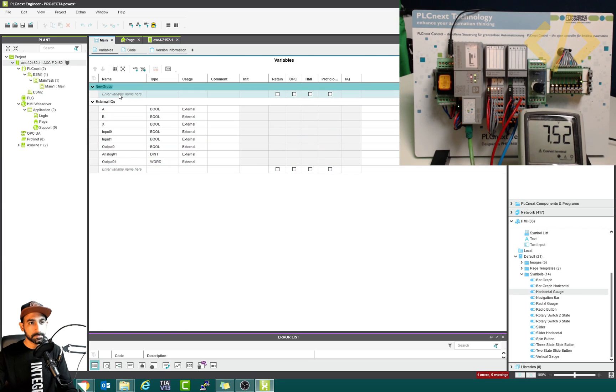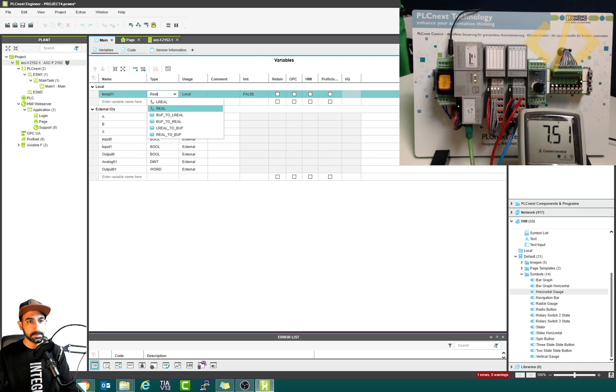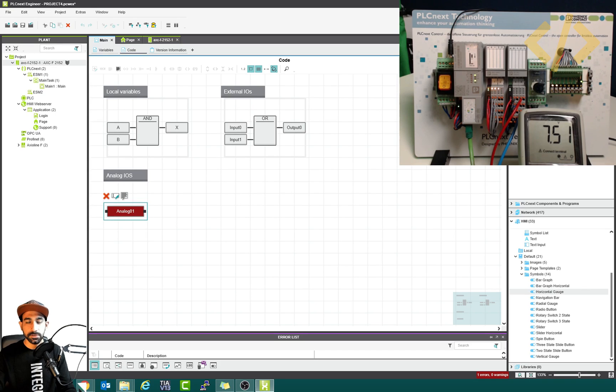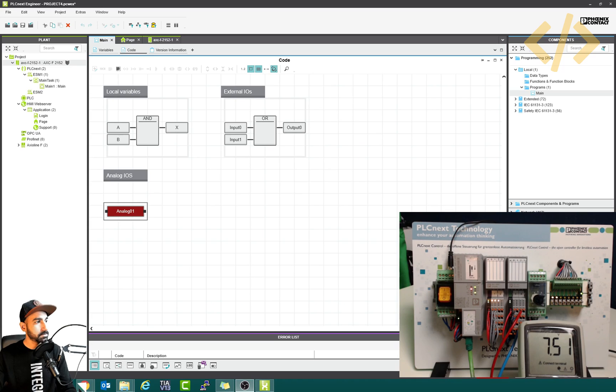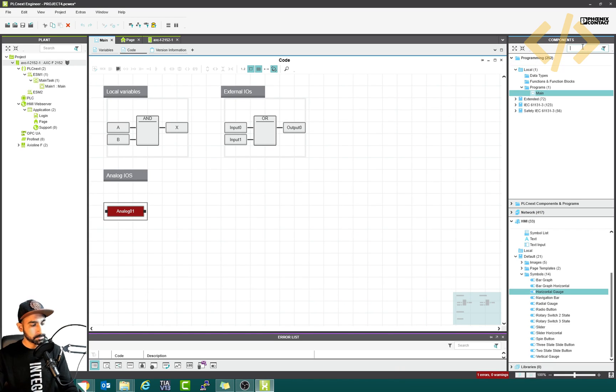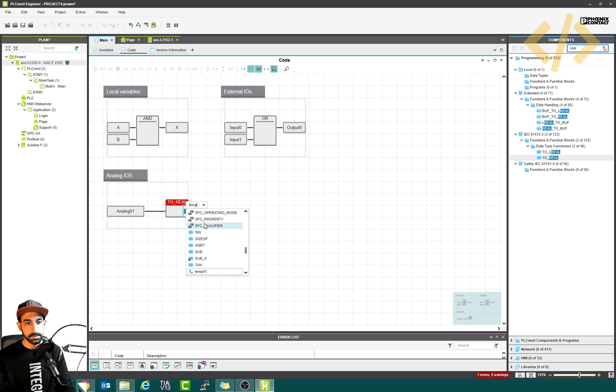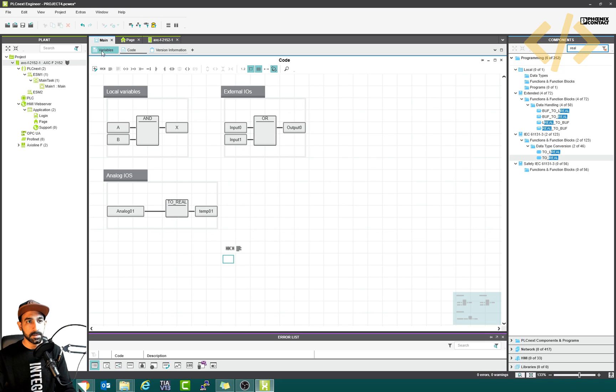Here I will create a new group and call it 'local'. I'll take a variable, let's say temp01, and set the data type to REAL — that's a local variable. I go back to my code and search for REAL, then 'to real'. I'll bring it here — this will convert the input to REAL. I need to give an output, which I just defined as temp01. So this will convert the double integer analog input into a real number.